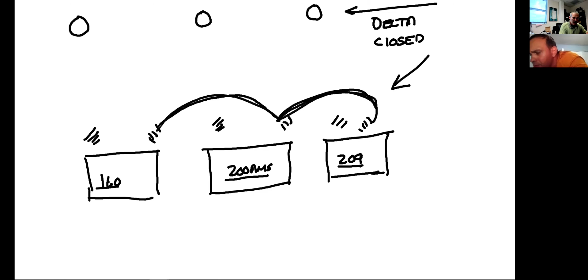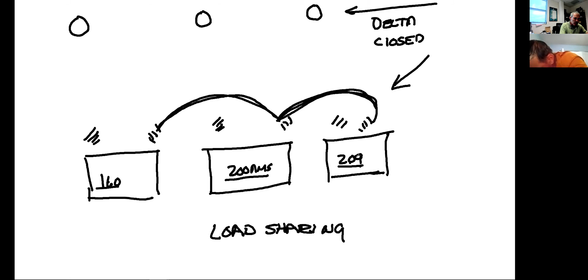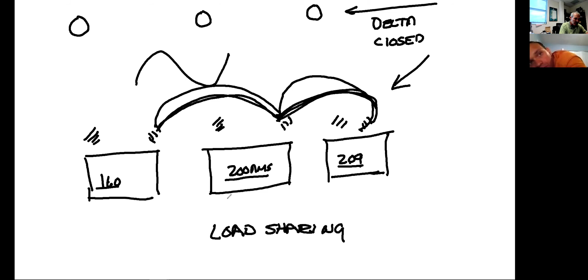Closed delta is very good at load sharing. So when I get up to 209 on this one, it's going to give a little bit to here, and a little bit to here, and that 200 amps -- the sine wave is sharing that load between all three transformers until you eventually see it pan out: 201, 200, 200. That extends the life and lets you use those transformers much longer and get more efficiency out of them.